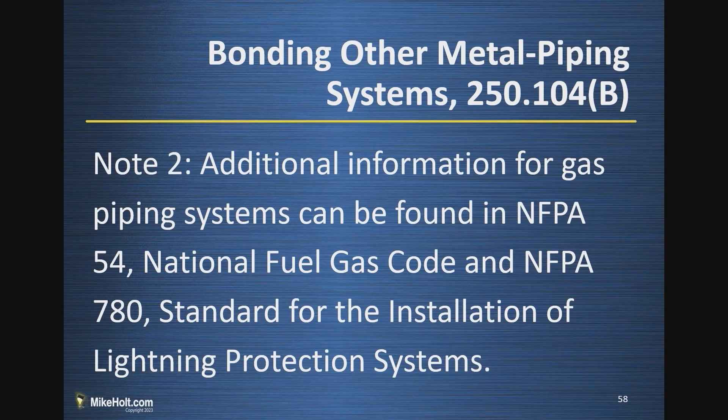There's an informational note that additional information for gas pipe systems can be found in NFPA 54, the National Fuel Gas Code, and NFPA 780 for the installation of lightning protection systems. NFPA 54 covers mechanical contractors doing mechanical work. NFPA 780 is the lightning protection standard, and NFPA 780 requires bonding of things that are within six feet.